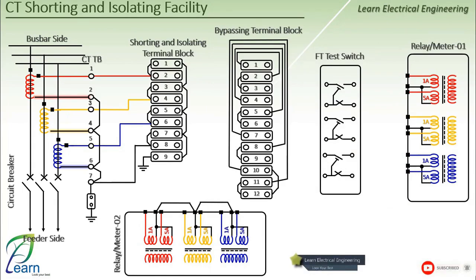Then I exit with 3-phase and enter the slide link TB, which is the terminal block responsible for the bypassing process. Bypassing TB is used in the case where I have 2 protection relays or 2 metering devices connected in series on the same CT secondary. For example, when you have the overcurrent and breaker failure as 2 separate relays connected in series, or when you have the BCU, which is the Bay Control Unit, and the DSM, which is the Dynamic System Monitoring, connected in series.